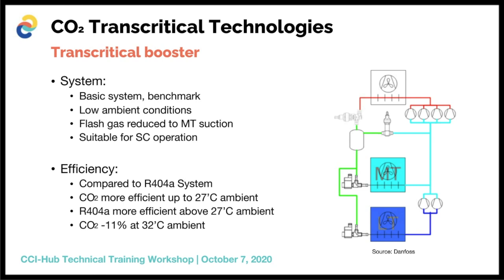For this application here, I have looked at ambient conditions of about 32 degrees Celsius to do energy efficiency comparisons, seeing that that is quite an average high temperature for the Philippine area. So basically, looking at a 32 degrees Celsius ambient, CO2 compared to 404A, when it's working as a transcritical booster system, is about 10% less efficient than a 404A system.